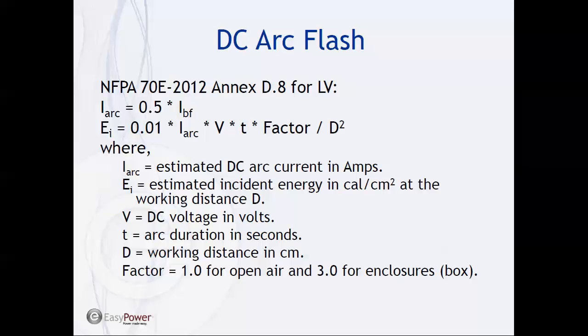In this equation, we have a factor which is going to be dependent on whether it's open air or enclosed boxes. So when you have an arc in a box, it's going to be 3 times higher than in open air.